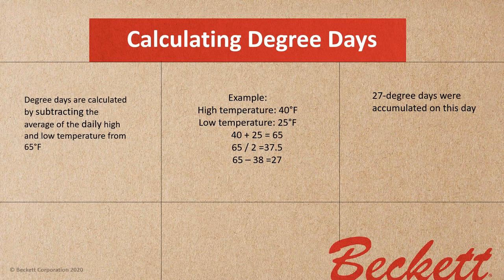Let's refresh our brains. Degree days are calculated by subtracting the average of the daily high and low temperature from 65 degrees Fahrenheit. In our example, the high temperature for the day is 40 degrees and the low is 25. We take 40 plus 25, which equals 65, divide by two to get 37.5, round up to 38, subtract from 65, and we end up with 27 degree days accumulated for that day.